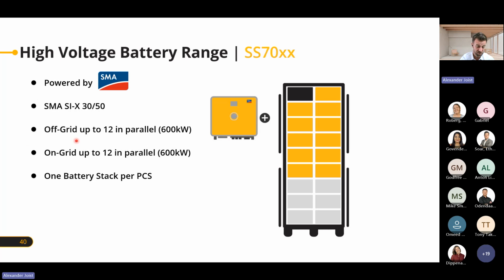The Sunny Island, for instance, also, because it's a 50 kilowatt inverter, it's a bit small for the cabinet because we would need a little bit less battery actually for this. So what you can do is you can actually connect 2 inverters to it, which is possible. So you can connect 1 on each side, let's say, and then you can split, or 2 on one side, also possible. And then you can split the battery, put 2 BMUs on top, and have for each inverter 1 battery. Makes it a bit easier.